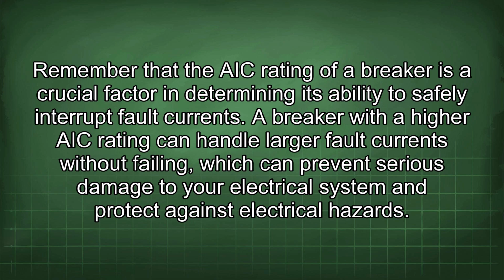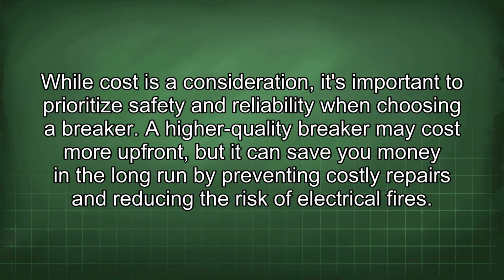Remember that the AIC rating of a breaker is a crucial factor in determining its ability to safely interrupt fault currents. A breaker with a higher AIC rating can handle larger fault currents without failing, which can prevent serious damage to your electrical system and protect against electrical hazards. While cost is a consideration, it's important to prioritize safety and reliability when choosing a breaker. A higher quality breaker may cost more upfront, but it can save you money in the long run by preventing costly repairs and reducing the risk of electrical fires.